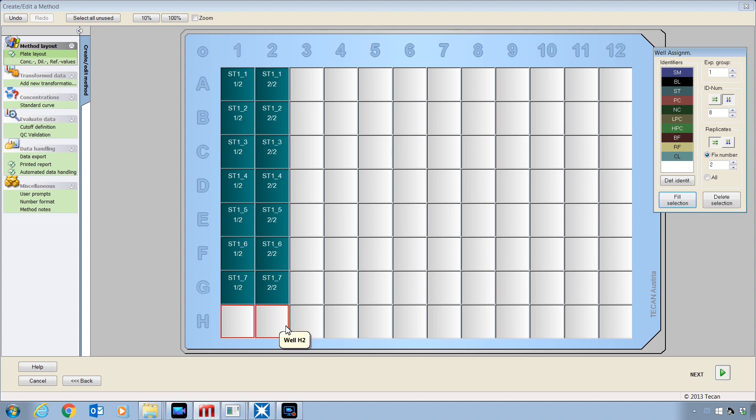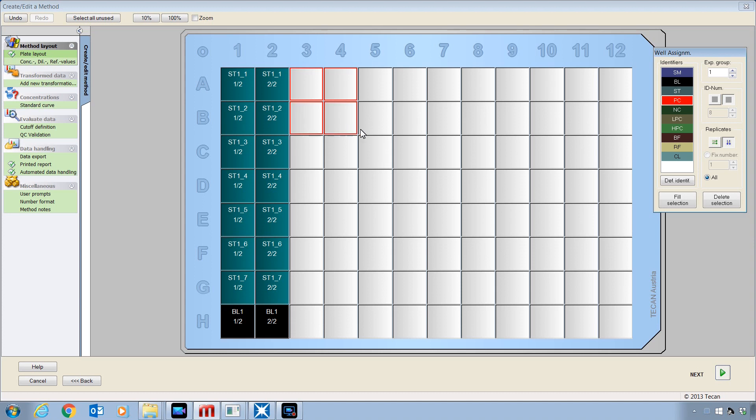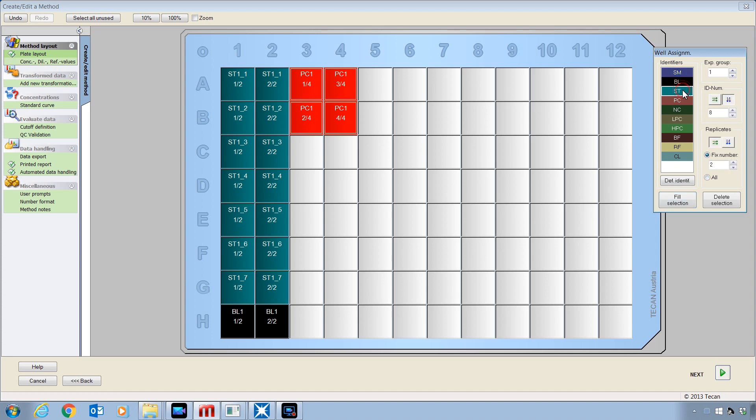The next step is to define some blank samples in wells H1 and H2. Note that when I pick BL, the software automatically replicated that identifier. It will do the same thing for other types of identifiers such as CL, RF, BF, and even the positive control. And that is because Magellan presumes that it is being drawn from a common stock solution and it automatically replicates all well locations where that identifier is placed. It is only for samples or standards that you have control of the replication as you can see here.